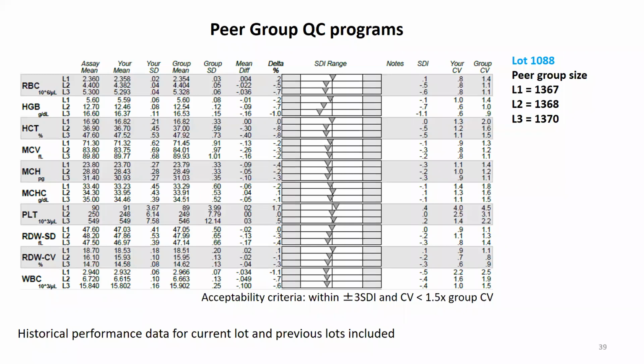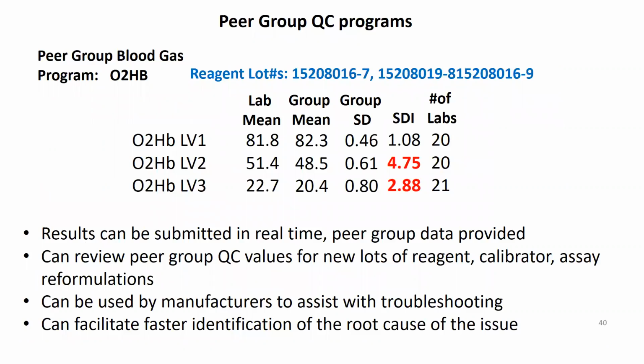So an advantage of this approach is that data can be accessed in real time. If the lab experiences an out of control event, the technologist can access the peer group QC data to determine if the lab's QC value is significantly different than the peer group. And if it is, that would suggest a problem with the laboratory's measurement system. This peer group QC program is for oxyhemoglobin results from a blood gas analyzer. We can see the SDI for our lab was high compared to the peer group for 2 levels of QC. So we could tell that this issue was isolated or specific to our lab. This was resolved by replacing a new cartridge of the existing reagent lot on the analyzer. So the issue was caught before it could impact patient care.